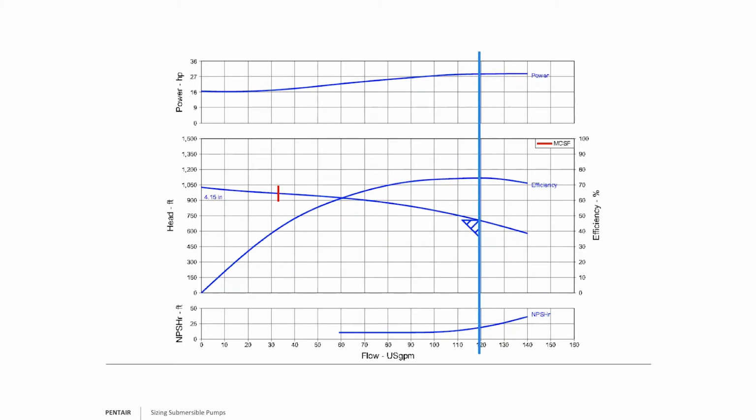Now, the pump is rated as a 120 gallon per minute nominal. 119, if you ask me, is pretty close, so I'm not going to argue with the manufacturer on that. At the total dynamic head, boy, I'd be guessing, and I would say, well, I think that the total dynamic head might be about 720 maybe.